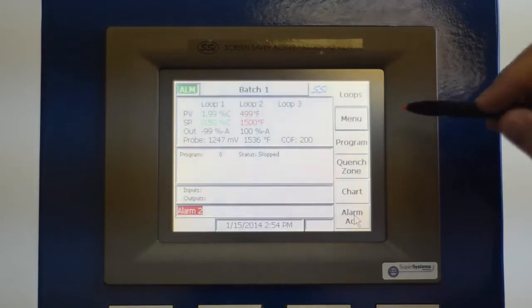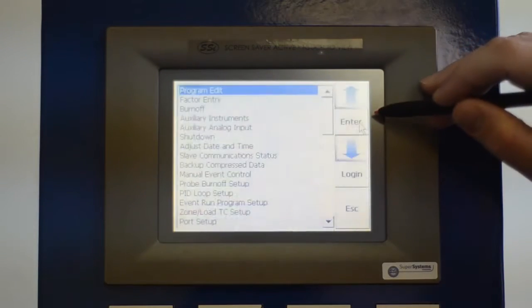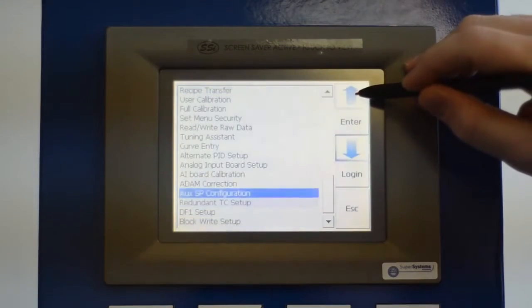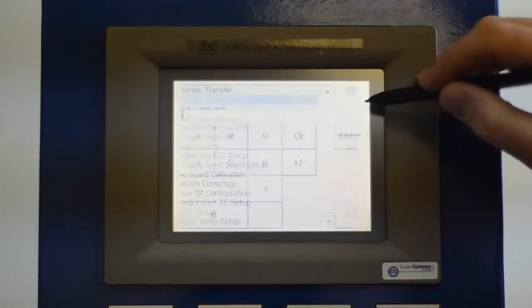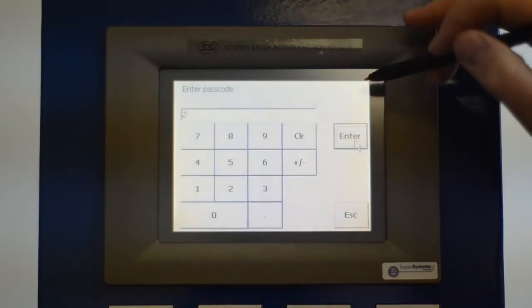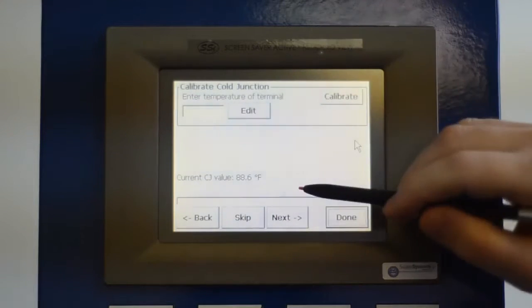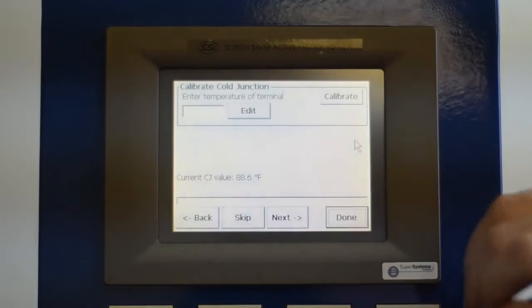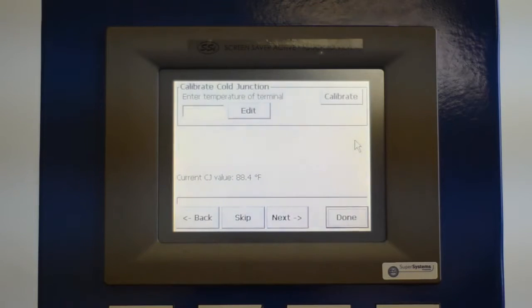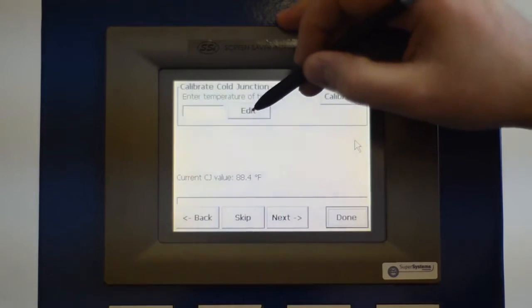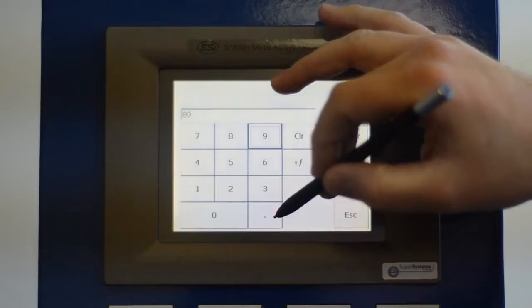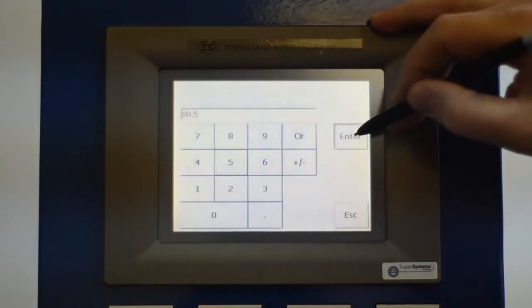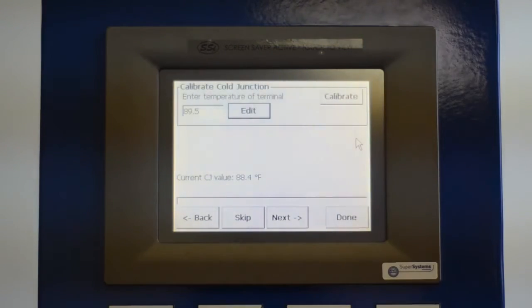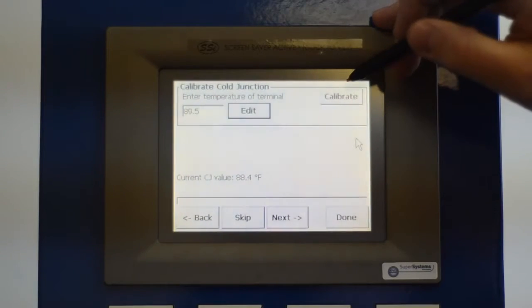So if we needed to adjust this again, we then just go back into our menu, select our user calibration, password is the number 2, and then we would just add that degree here to the temperature that it's currently reading. So the current reading of 88.4, 88.6, it's fluctuating a little. We can then just add 1 degree to that value, select our edit button, 89.5, we'll split the difference between the 4 and the 6, and we'll select calibrate.